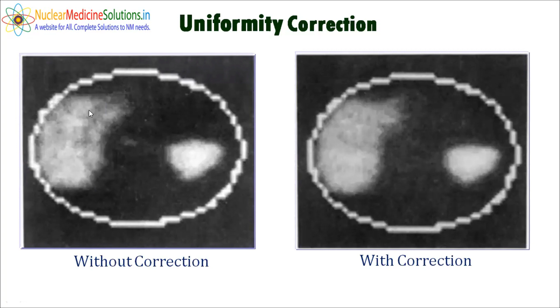You can see here, this is the image when we have not applied any uniformity correction map in the gamma camera. So we are getting a non-uniform image, which becomes uniform after applying the uniformity correction map. This is the second example, where without the uniformity correction map there is a bad image or a cold area in the image, which disappeared after applying the uniformity correction map.